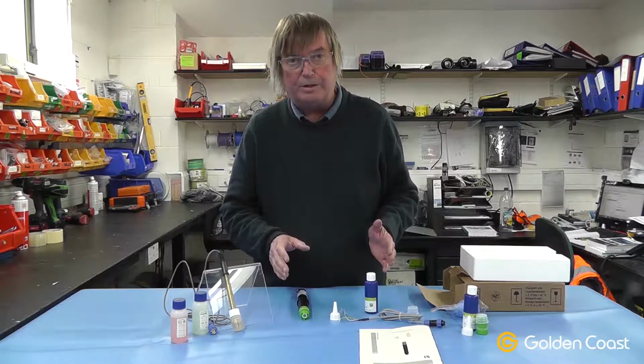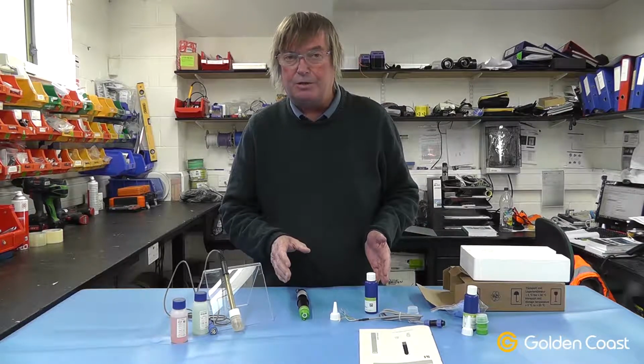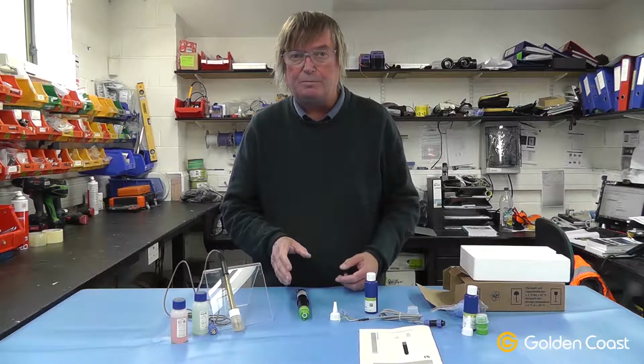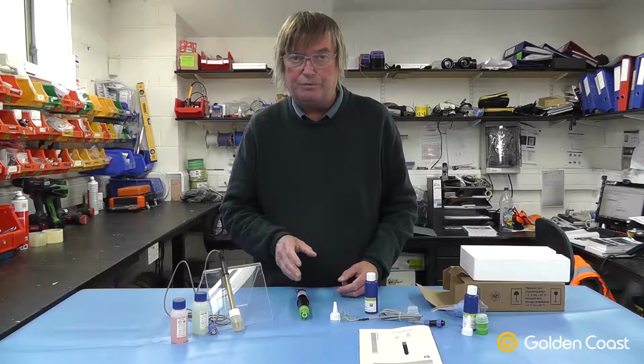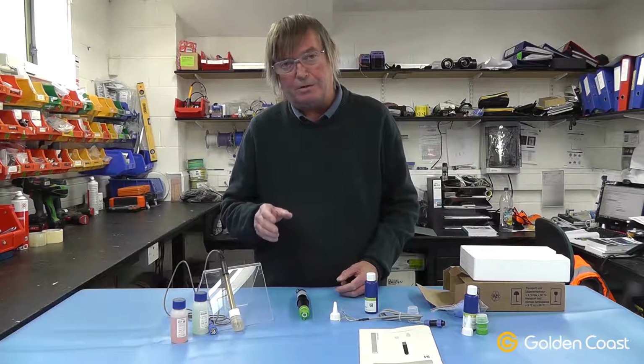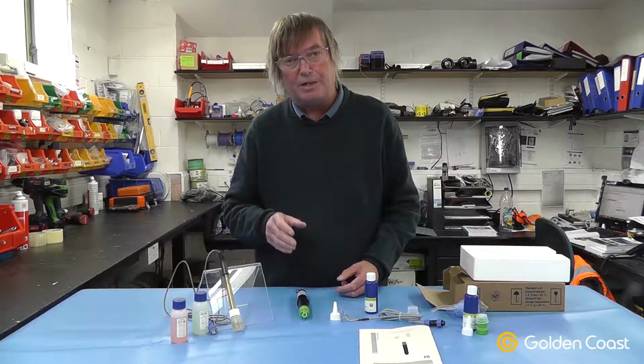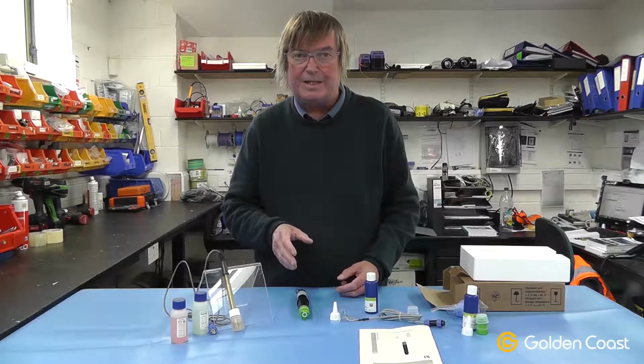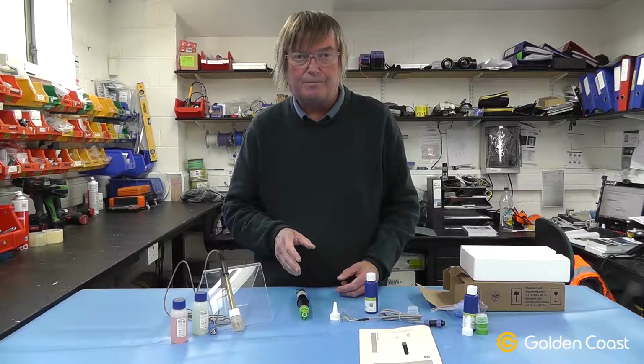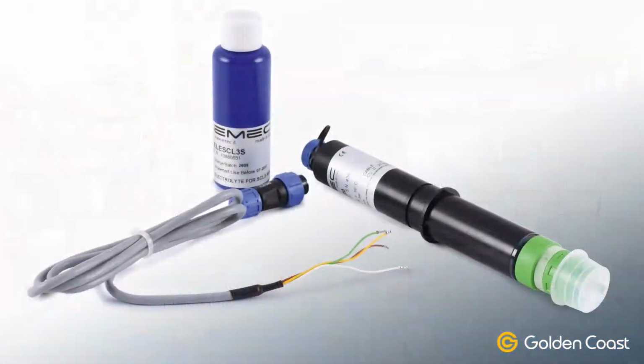So this is a free chlorine probe. It will measure the actual chlorine in the water, so you will get a parts per million reading on the screen of your controller. Unlike the redox probe, which was just measuring the potential of the water, this measures the actual chlorine within the water. So that is the commercial systems for the Crystal dosing. If you have any further questions on this or require any further help, please contact us in the usual way.